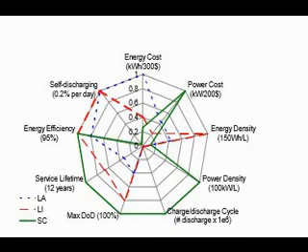Higher energy density is one key reason that lithium ion has been proposed for use in UPS servers, which have form factor constraints. In lead acid, lithium ion, or other batteries, energy is stored in a chemical reaction. In contrast, a supercapacitor only stores energy as opposite electric charge on the storage medium surface. This different energy storing mechanism means that the energy density of a supercapacitor is lower than that of a battery. To provide the same capacity, a supercapacitor has 5 times larger volume than lithium ion. Therefore, it is desirable to reduce supercapacitor requirement in a form factor constrained environment.